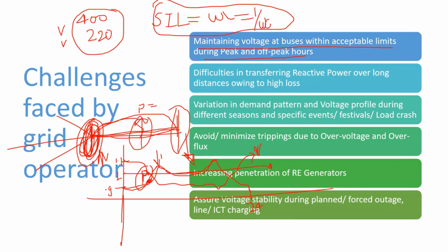However, the grid operator can only do his part when proper planning is there and he has been given adequate resources to maintain this reactive power. Unless you provide the reactive power equipment or resources to the operator, he will not be able to maintain it on his own. There will be a chance that he will be operating out of the operational limits, out of the acceptable limits. That will be a vulnerable situation for the operator. So we need to have very good planning. On the operation side, there is good flexibility for the system operator.